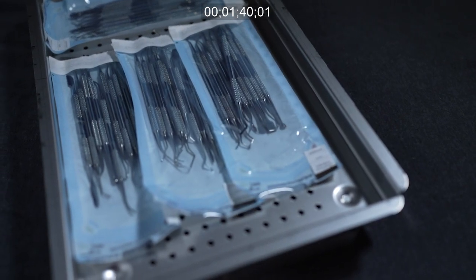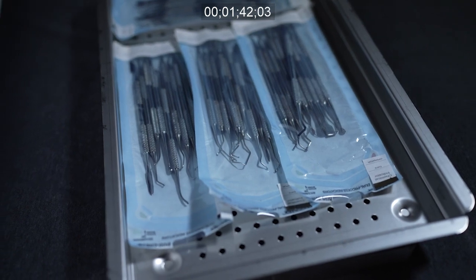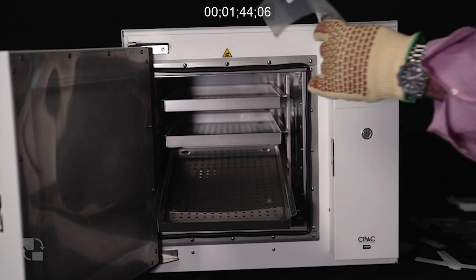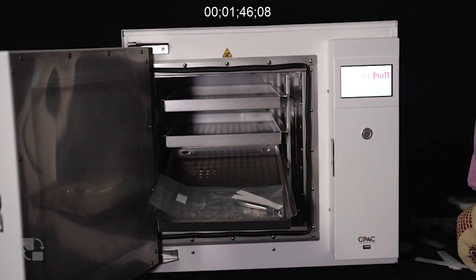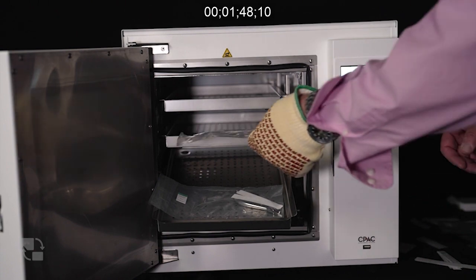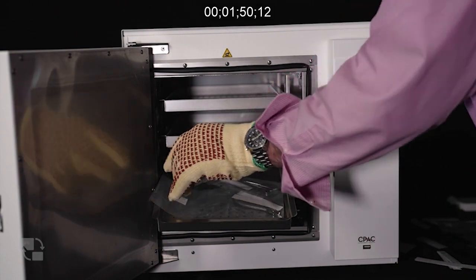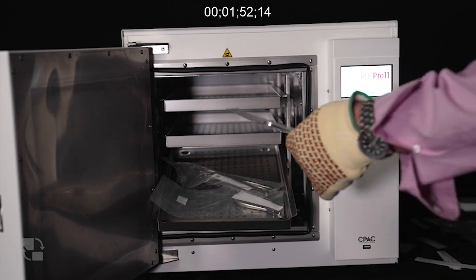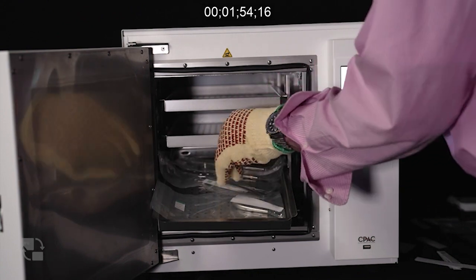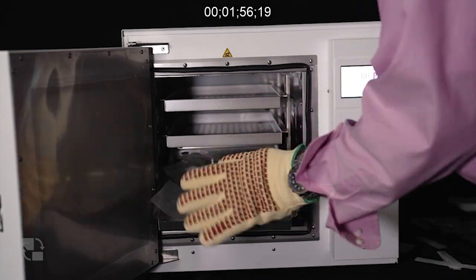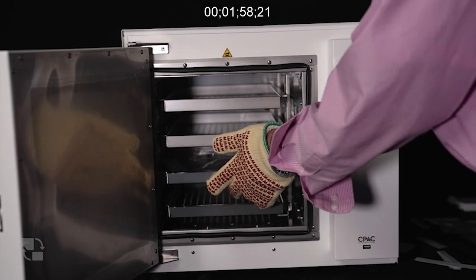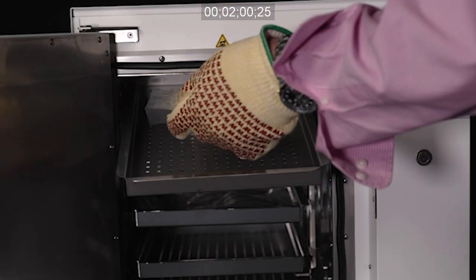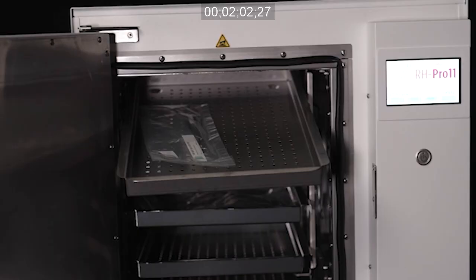In preparing your load on instrument trays, arrange the load in a single layer of cleaned and dried instruments, cassettes, or packs. When wrapping instruments for the 375 temperature cycle, use only high-temperature sterilization pouches and wraps that have been validated for use either by the manufacturer or by Cpac for sterilization at the 375-degree temperature.